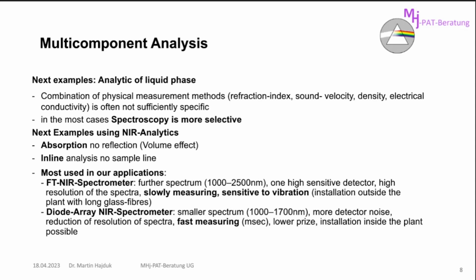Another possibility is a diode array NIR spectrometer. We have a smaller spectrum, 1,000 to 1,700 nanometers, sometimes also to 2,000 for a special detector. In this case, we have more detector noise. We reduce the resolution of the spectra, but we have a very good point. It's very fast.